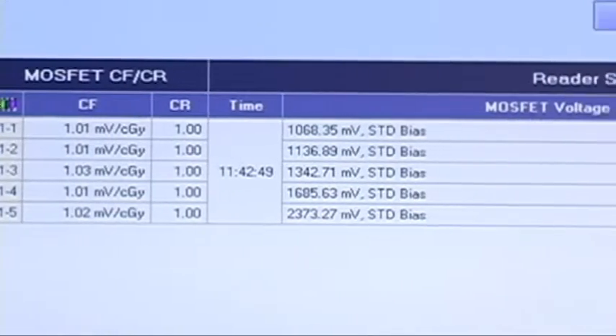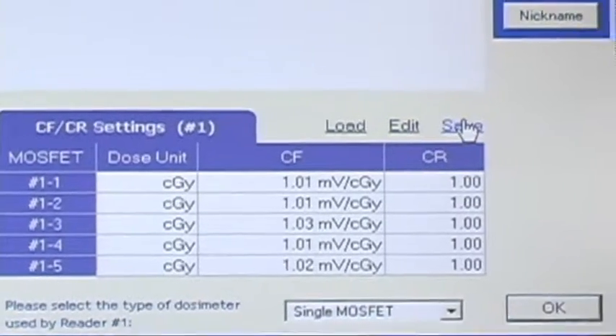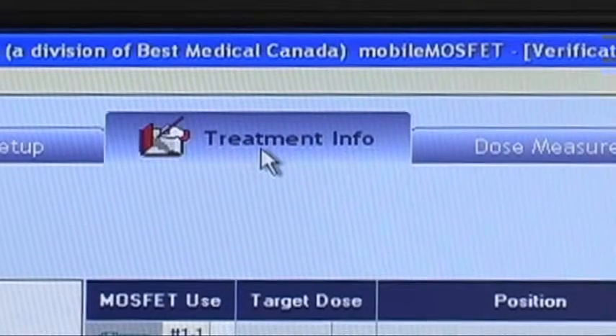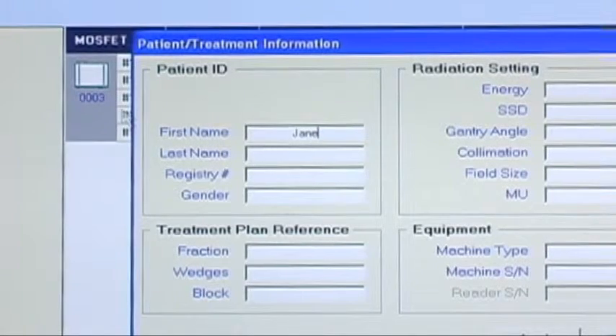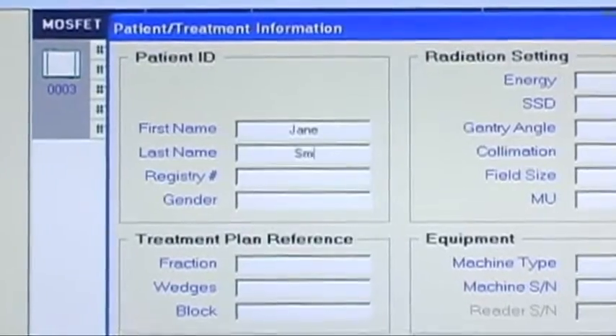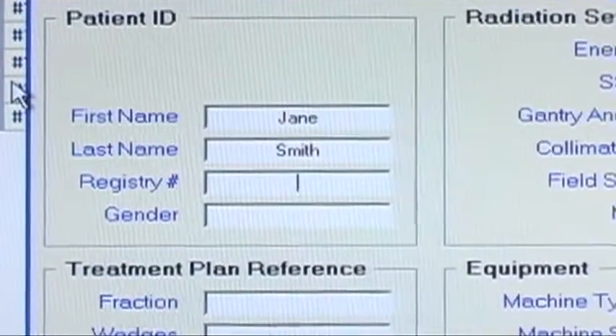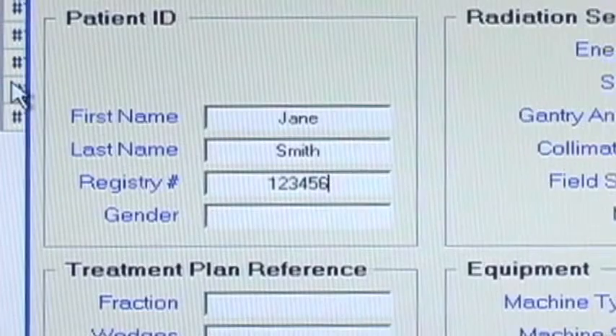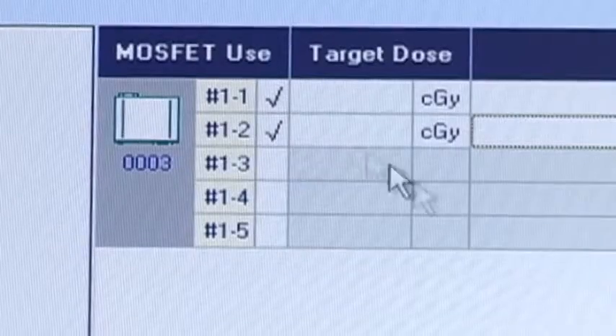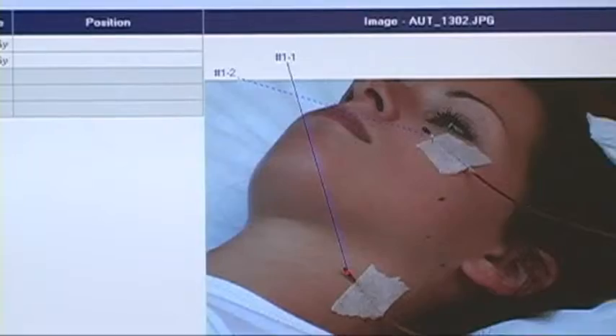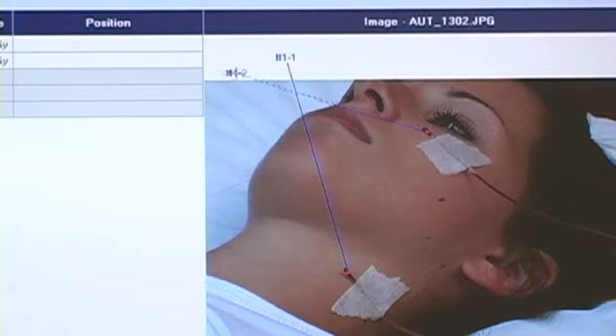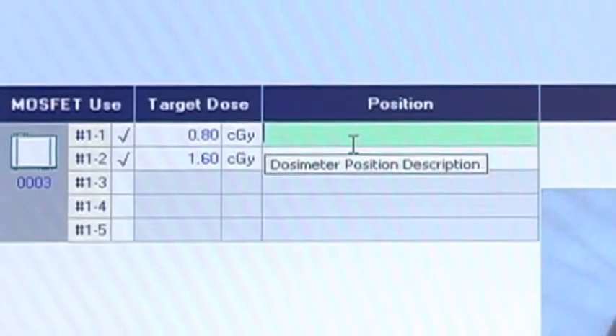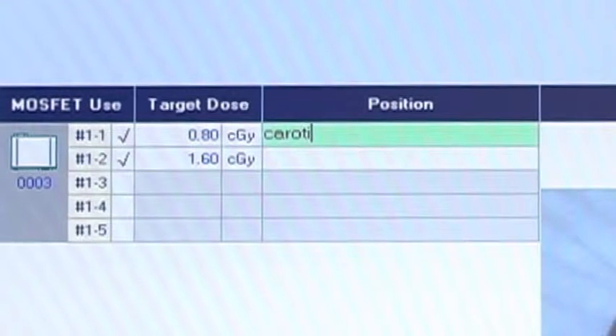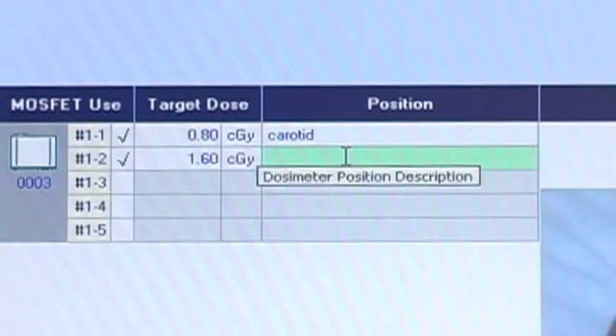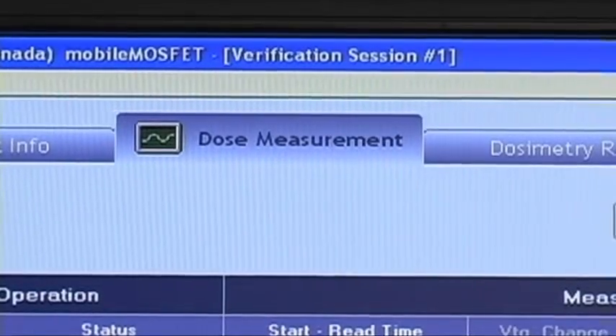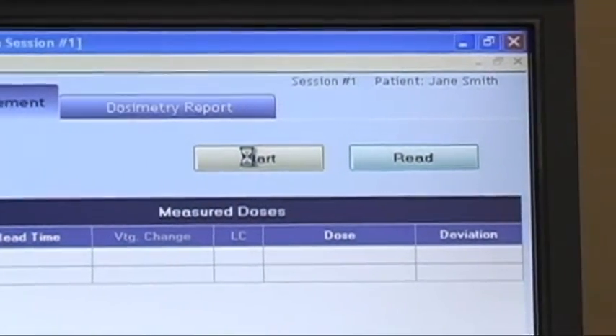With this screen, the user can load, edit, and save calibration factors. The treatment information screen is used to enter patient data such as first and last names and registry number. This data is then automatically included in the dosimetry report to be put in their chart. A key feature enables the user to enter in the target dose and MOSFET locations. These information labels can then be dragged onto a JPEG or bitmap image, indicating the locations of the MOSFET sensors on the patient. The dose measurement screen is used to initialize the dosimeters.